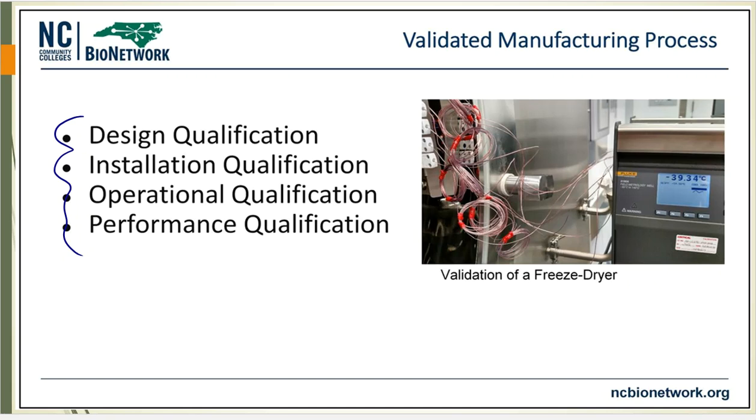Okay, well, no one's going to be asking those types of questions, but for equipment and for manufacturing purposes, these pieces of equipment need to be able to do a job, and we've got to qualify them in order to do the job and to be used. And there are 4 stages of qualification here. The first one is design qualification. The second one is installation. The third one is operational. And the fourth one is performance.